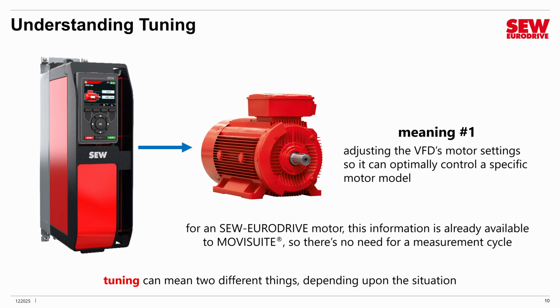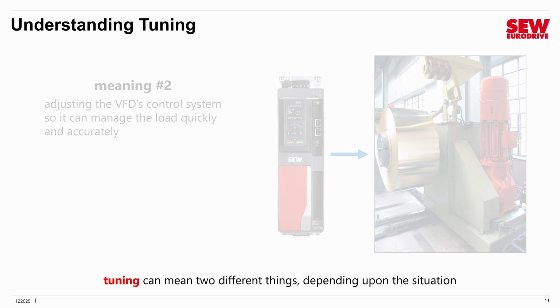Now, with SEW Eurodrive motors, you never have to do this. You never tune them using type 1 tuning, and that is because MOVISUITE already knows all the electromechanical information of all our motors. It therefore never needs to run a measurement cycle. All right, so that's type 1 tuning. Let's move on to the other type. This is the one we're going to do in this lab activity, and this one has nothing to do with the brand of the motor that you're using.